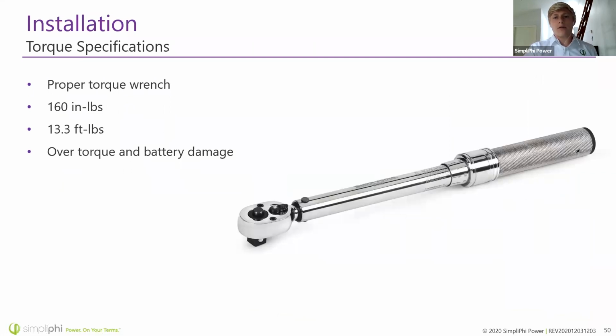When you're tightening down the nuts on the battery terminals, make sure to use a calibrated torque wrench, not a socket wrench. I've seen too many people recently forget to calibrate their torque wrench or over-tighten using a socket wrench. I've even seen a couple of people snap off a terminal. In my opinion, you'd have to really be going way too hard to do that—it's pretty easy to avoid as long as you're using a torque wrench.